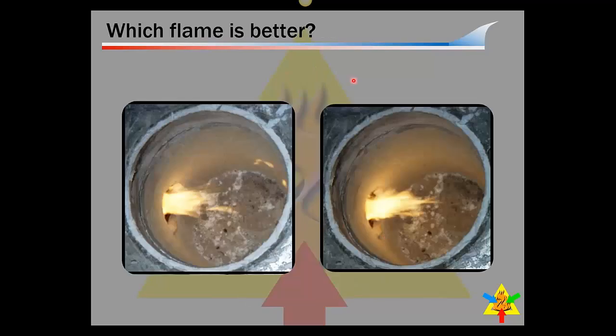So what I want to start with is asking you guys this question. Looking at those two flames, and this is a drum heat exchanger looking from the top down, can anyone tell me out there which one of these flames is the better burning flame? Left one or the right one? Don't all answer at once. Left? Some of you are saying left? That's my guess. Okay. Well, the thing here is that it's impossible to tell by looking at the flame, okay?